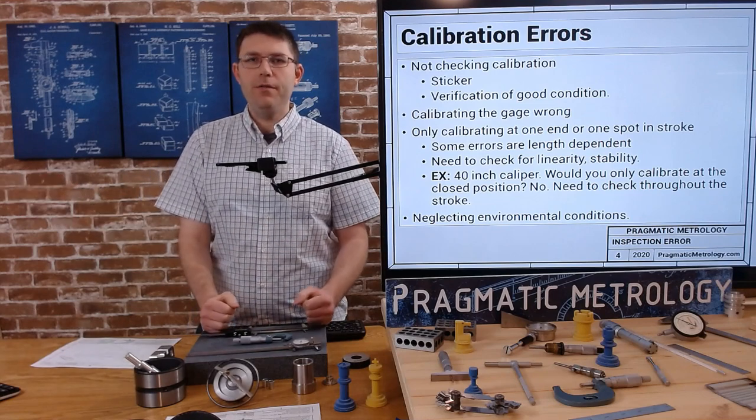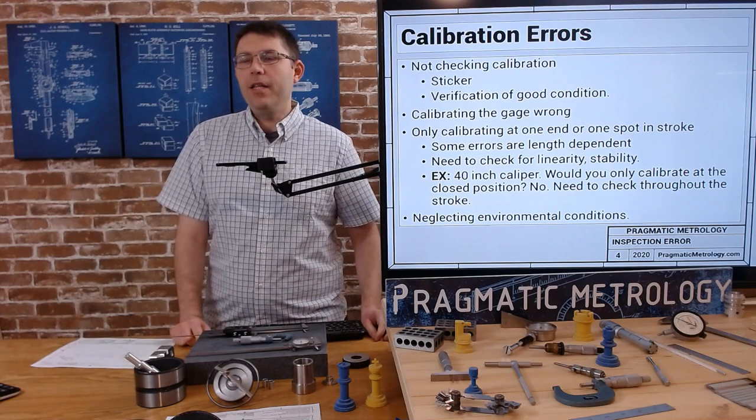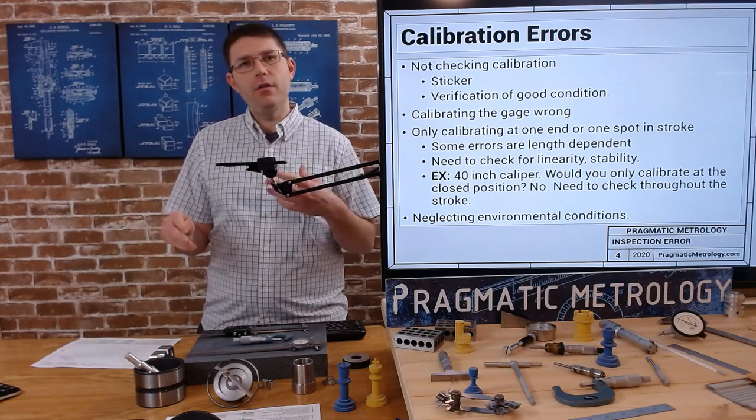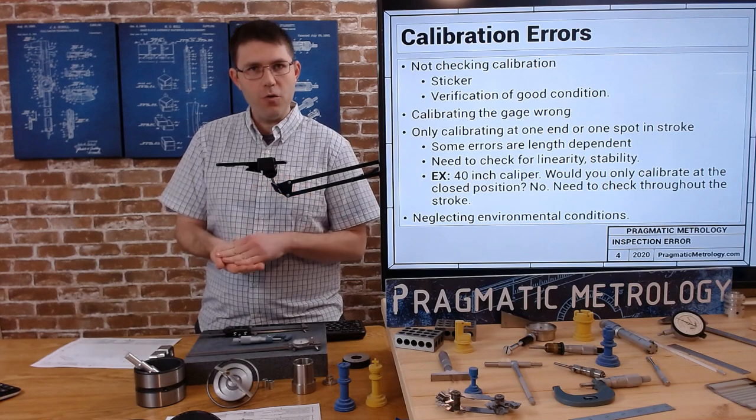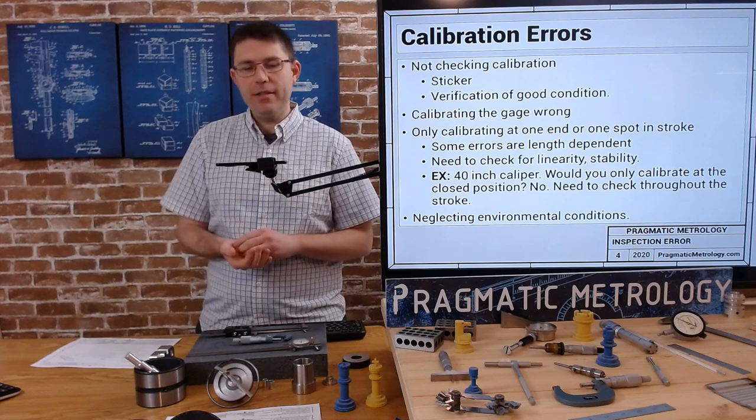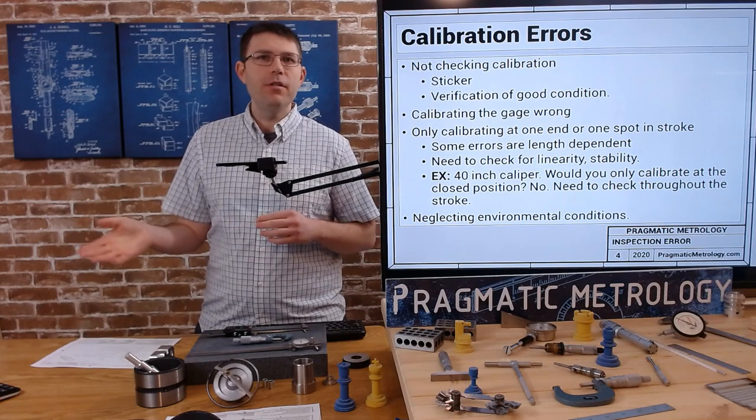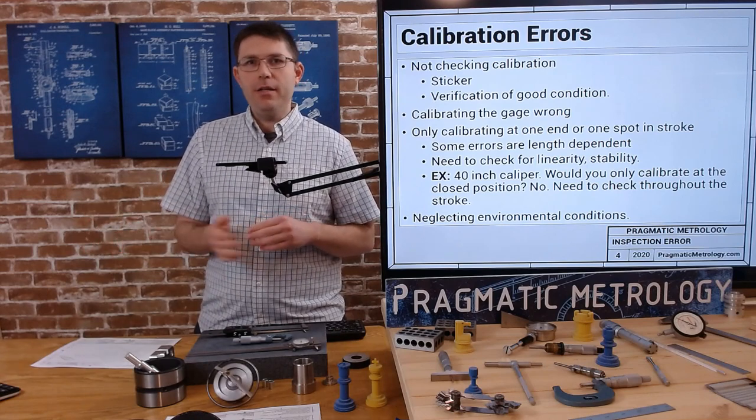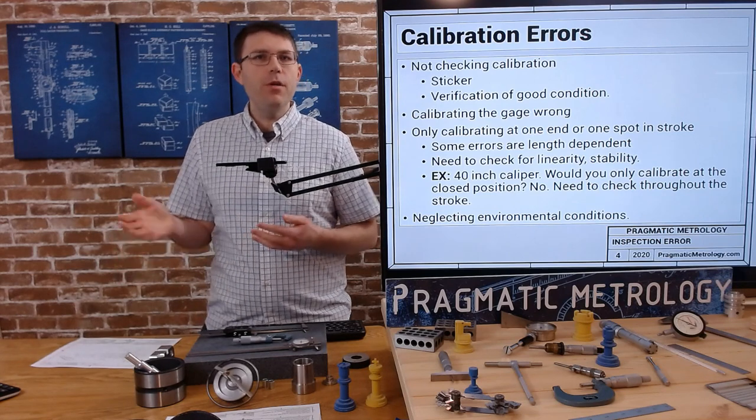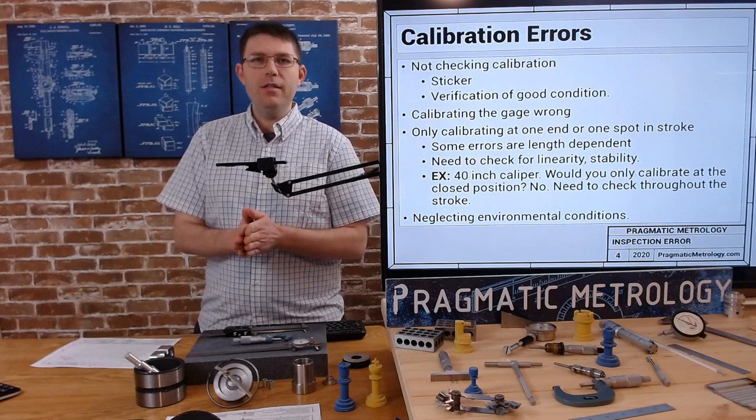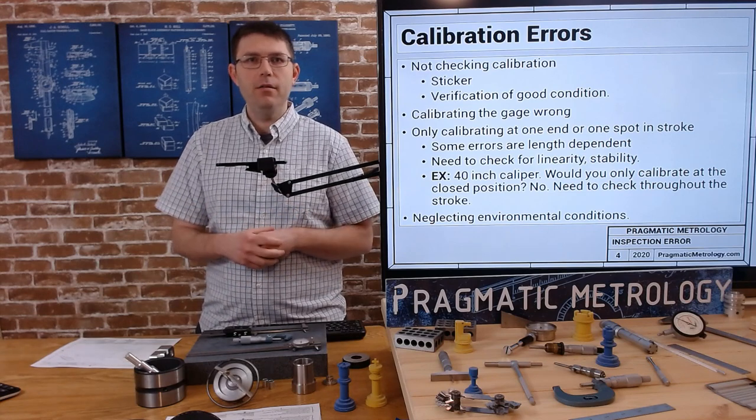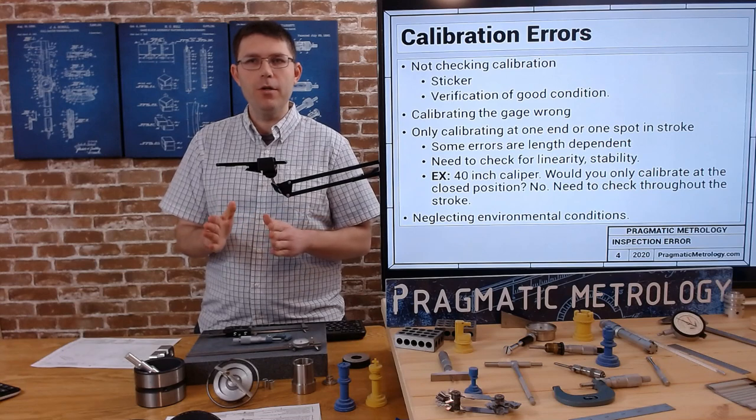Neglecting the environmental conditions when you're calibrating - every calibration should be under a controlled environment, a consistent temperature. You don't want to calibrate these things at 100 degrees Fahrenheit in the summer and 60 degrees Fahrenheit in the winter. You want to try and calibrate things at the same temperature year-round and use them at the same temperature year-round within some allowable margin.